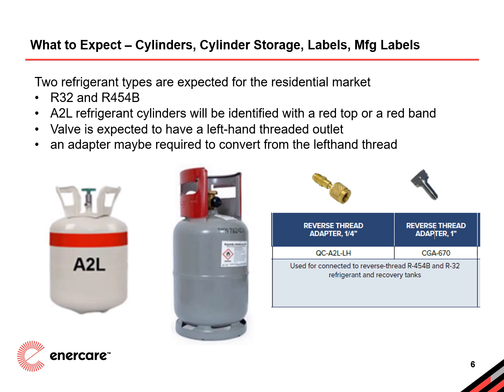Some of the threaded connectors on these cylinders are expected to have a left-hand threaded outlet. This is a deliberate safety measure to prevent cross-contamination with non-flammable refrigerants. Because of this, you may need an adapter to connect your equipment, and it is something to keep in mind as we transition to these new refrigerants. The adapters shown here will help you bridge the gap when working with reverse threaded connections. It's a small adjustment that ensures compatibility and safety, reinforcing the care we take in every aspect of our work.